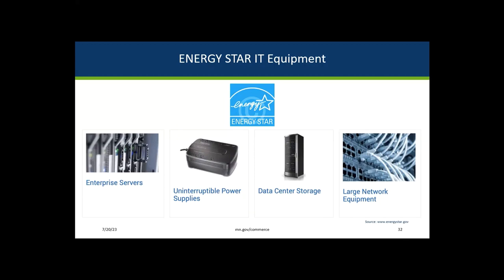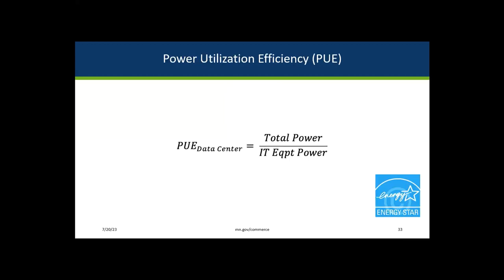Energy Star has, however, developed an energy performance rating system for data centers that could be useful for intelligent building systems. The metric is called the Power Utilization Efficiency, or PUE. The PUE is a standard measure of facility infrastructure efficiency in the IT industry. It is a measure of how much energy is consumed by data center infrastructure equipment like power supplies and cooling, relative to the amount of energy delivered directly to the IT equipment. That is, PUE equals total facility power divided by the power of the IT services.